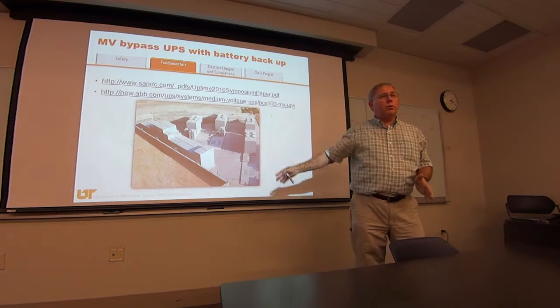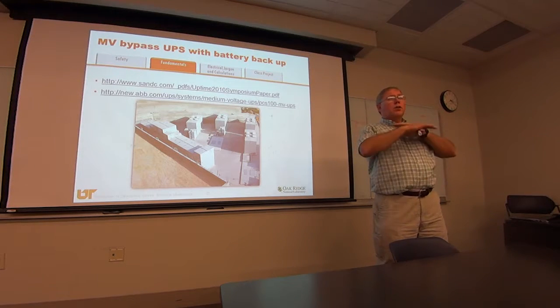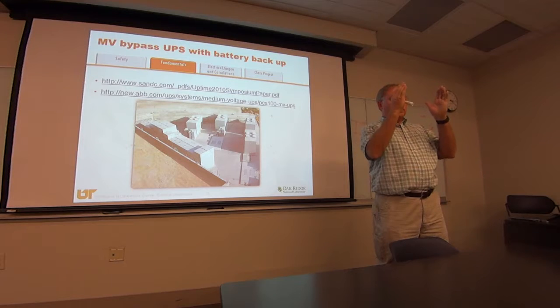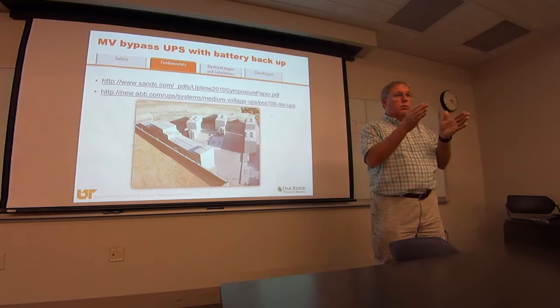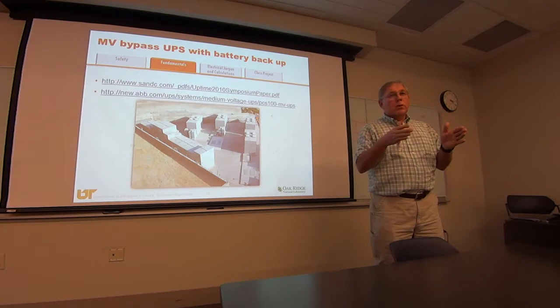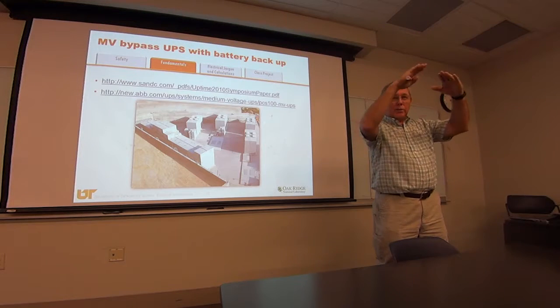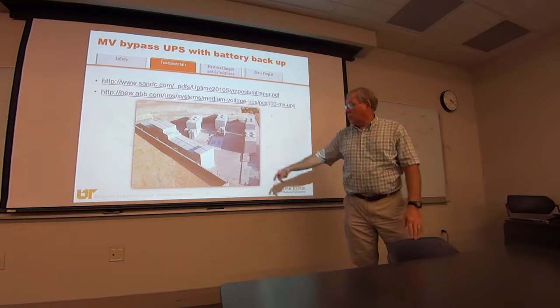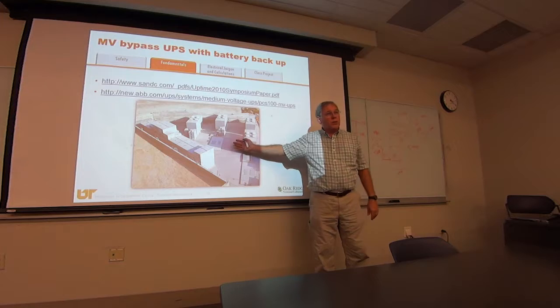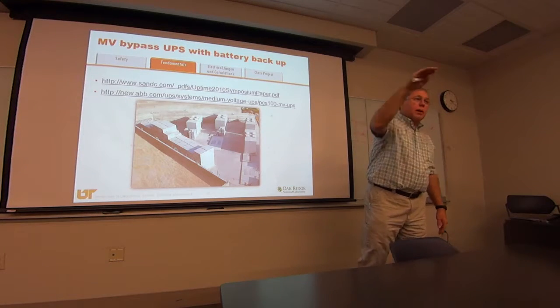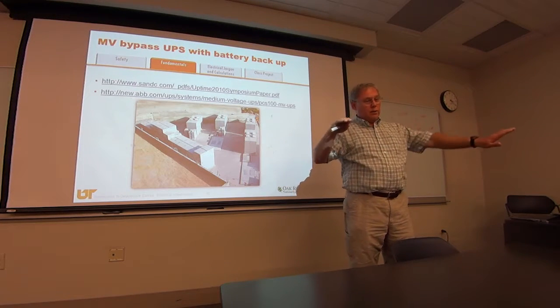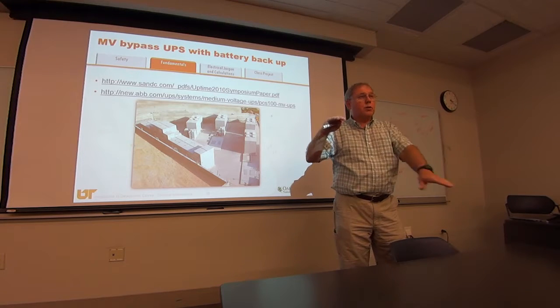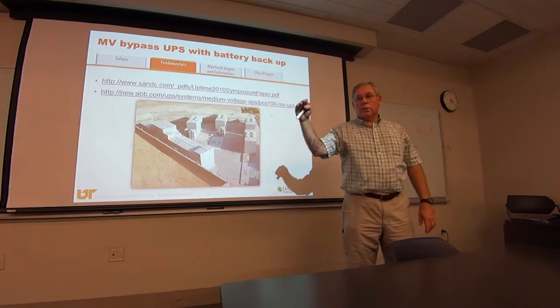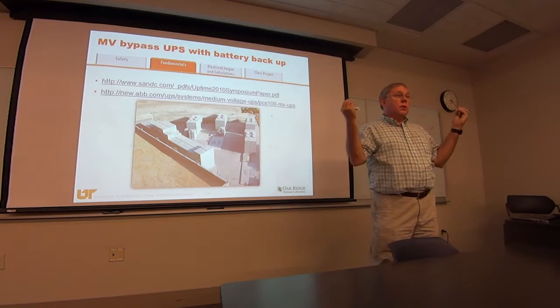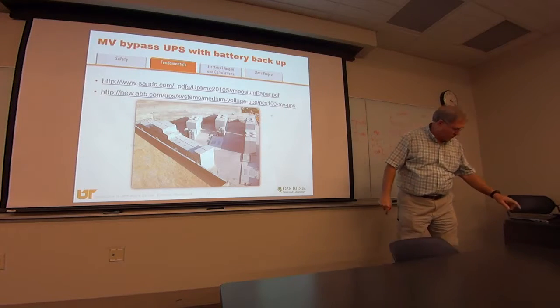Now, most of your computer stuff, you can cut the power completely off and cut it back on for a quarter cycle, and it'll ride through it. Just about all your stuff will, because it just can't deplete the energy in the capacitor banks that fast. So this thing right here works good. It's very efficient. By going through the static bypass and not through all the electronics, instead of having a 96% efficiency, you got a 99% efficiency. So if you're talking about 10 megawatts, that adds up to a lot of money.